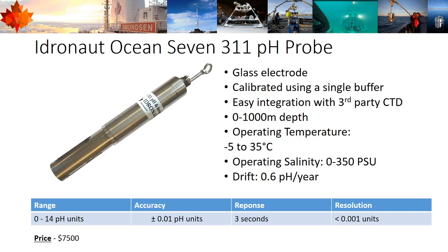The Idronaut 311 uses a glass electrode method as well, same as the YSI. The probe is very user-friendly, with just a single buffer for user calibration. It also easily integrates with third-party CTDs, so it can be configured to integrate with the monitoring systems that your lab may already have in place, or the sensors that your lab is already pretty comfortable operating.